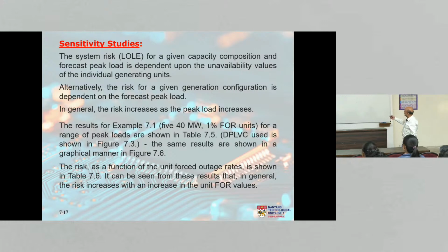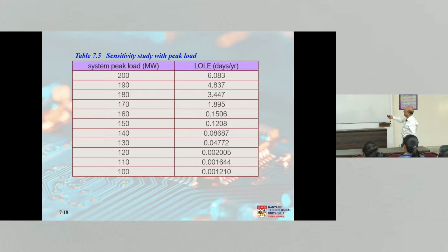So let's go back to this system with 5 40 megawatt units, 1% forced outage rate, and we change the peak load. You see 160 megawatt peak load, this was our risk, remember? From the previous example, we found the risk to be 0.15. Now I change the peak load to 200, the risk becomes 6 days per year. And if I reduce the peak load to 100, it's only 0.001 days per year. So you can see the variation. Now we can quantify the risk.